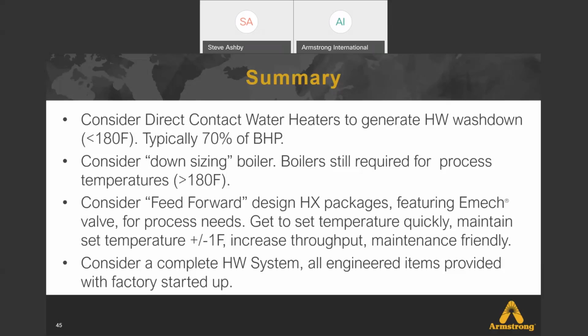For washdown, it makes sense to look at direct contact heating as an option. For your process water, consider feed-forward designed heat exchanger packages featuring the Emech valve for process needs. Again, get to temperature quickly and maintain that set temperature of plus or minus 1 degree. And consider a complete hot water system, all engineered items provided with factory startup.